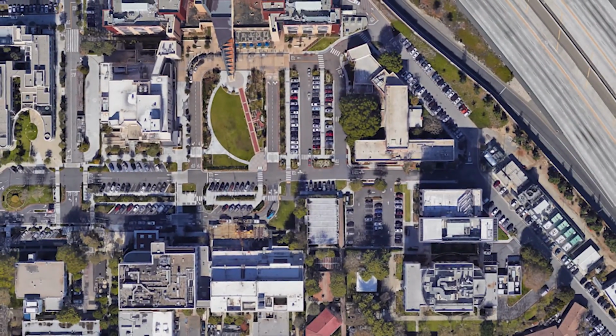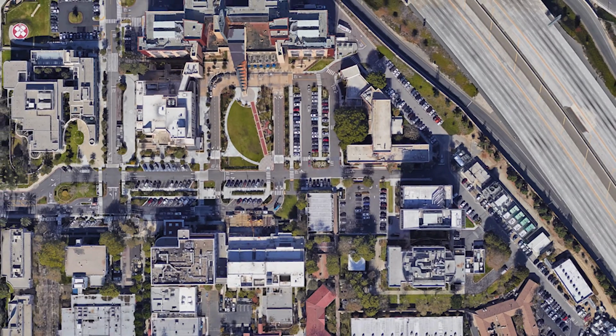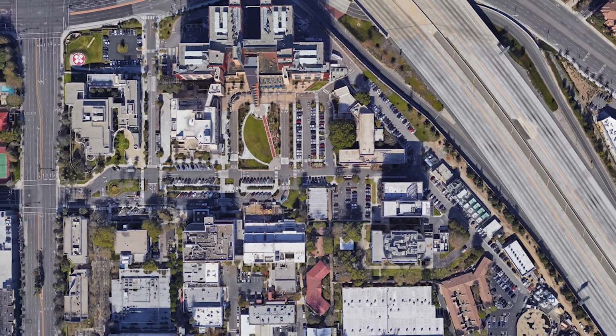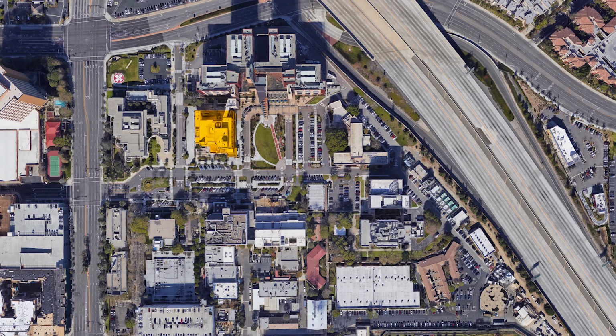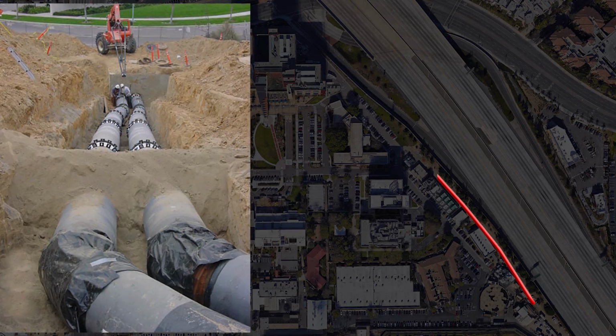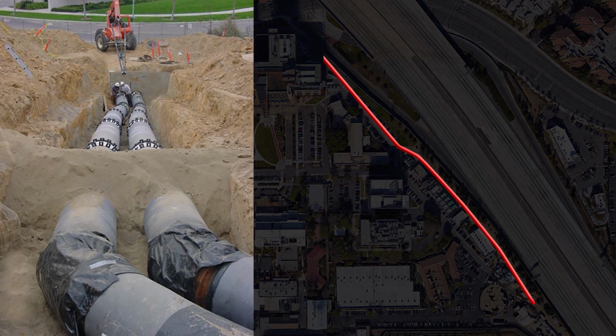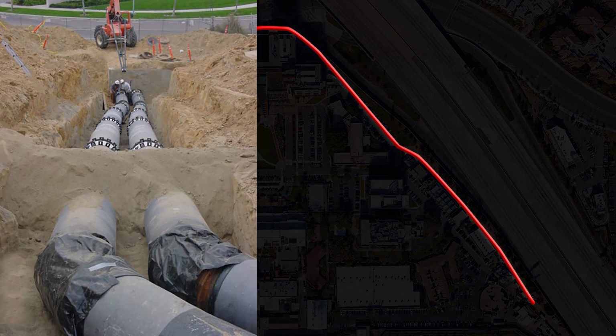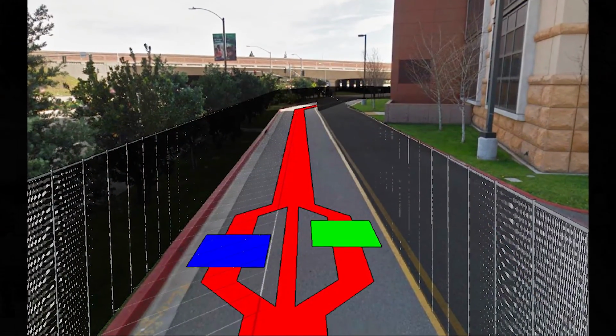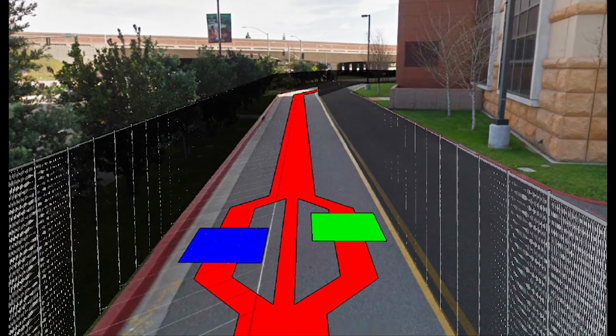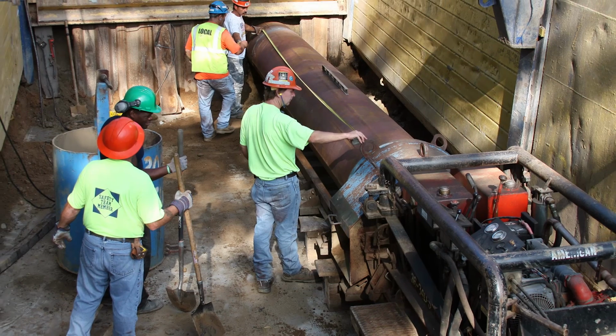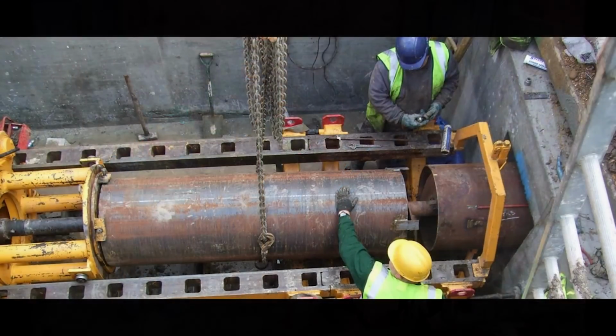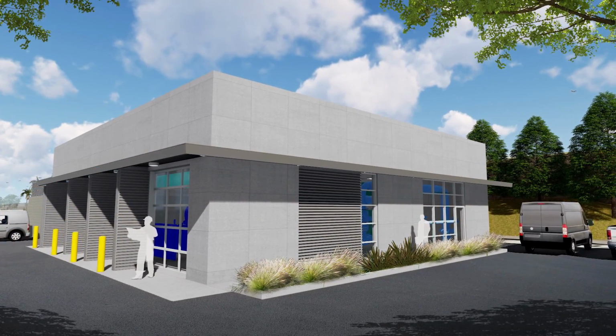We will now share our proposed design for the utilities that are being provided to meet the chilled water, oxygen, and normal and emergency electrical demands of existing buildings 1A, 3, 31, and the future emergency expansion department building. Our design utilizes a common trench to route chilled water and oxygen piping and normal and emergency electrical infrastructure to the subject buildings. The work will be undertaken in phases to minimize open trenches and keep a single lane open for through traffic. Our design also eliminates expensive boring through the central portion of the campus and uses the savings towards building a new central plant for the campus.